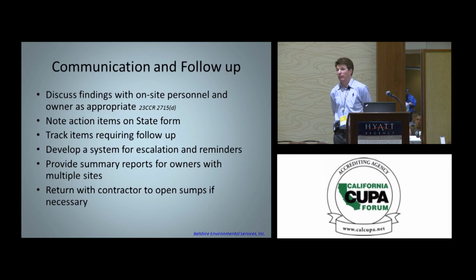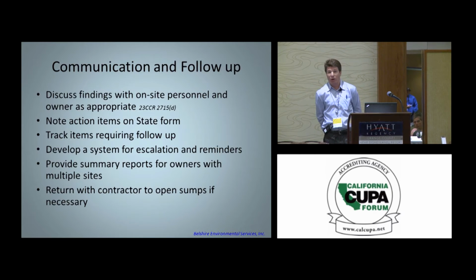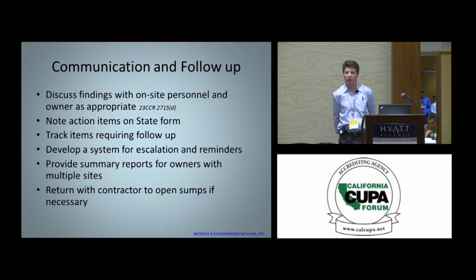Okay, so be glad to hear from the group, but my opinion on that is that person certified that the sensor was operational in the right position at the time they tested it. This is a later date, and if it's fallen over on its side, I have not seen, and I'm glad to hear from you all, where it says that I can't pick it up and put it in the right place, that it has to be a technician doing that.